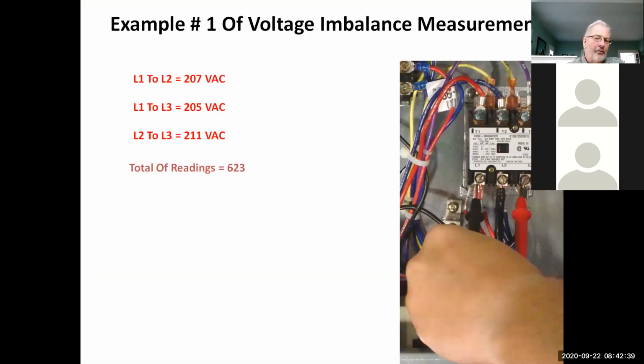One of the reasons that that's very important is winding resistance. I thought I had the sheet up here, but I don't. If you're within that 2%, your windings are going to run at a certain temperature. So for every 1% that you're over, if you're at 3%, your windings are going to heat up by 8 degrees. So if you're off 4%, you're going to get 16 degrees. You're going to start to overheat this, and you're going to start to lose compressors. So if you're losing compressors and you don't know why, this could be the whole reason.